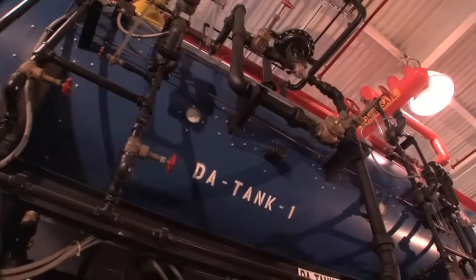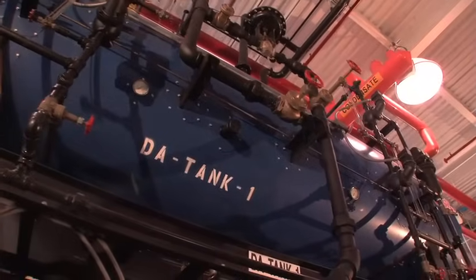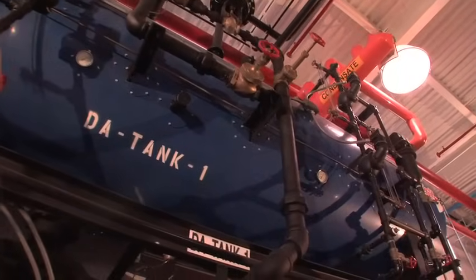The other thing is the old boilers were running almost continuously in low fire position because they just didn't have any modulation capability — no turndown. And that's one of the things that almost every hospital has: a high load swing. Hospitals typically have periods of the day where they are generating a lot of hot water for surgery sterilization, cooking, and you'll have periods where they run the boilers pretty hard for only two or three hours a day.